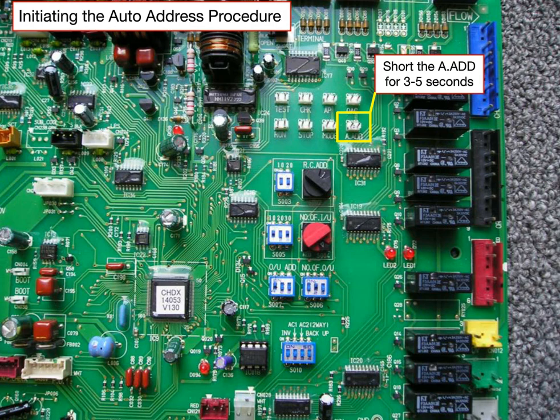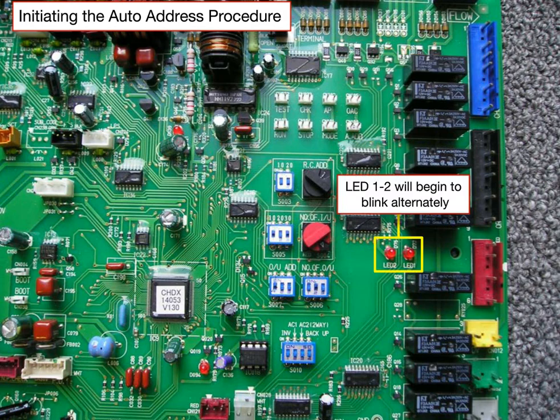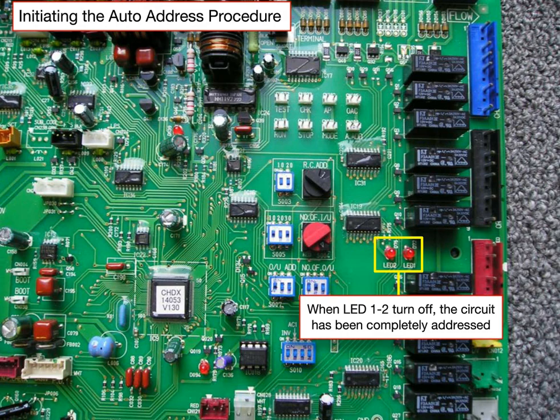Once you have configured all of the necessary settings on the main and sub-circuit boards, you are ready to auto-address the refrigerant circuit. Simply short the pins labeled A.ADD for 3 to 5 seconds. When the auto-address procedure has been initiated, LED 1 and 2 will begin to blink alternately. Once the LEDs begin blinking, you may release the short on the pins labeled A.ADD. Once LEDs 1 and 2 turn off, the refrigerant circuit has been completely addressed.